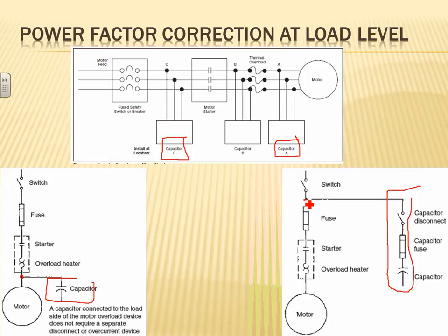You can see where they're tying it. You can put a controller on it where it only starts when the motor is running. So you can control that one here, put a controller on it. So when that motor starts, the capacitor starts. When the motor is not starting, the capacitor will not start. So these are where we get involved in sizing a capacitor to solve the power factor problem right at the offender level, the rich man's way.